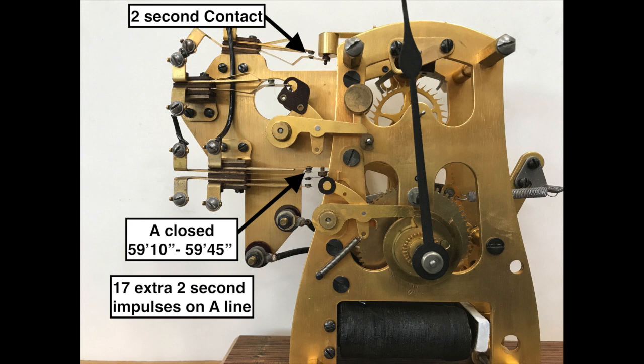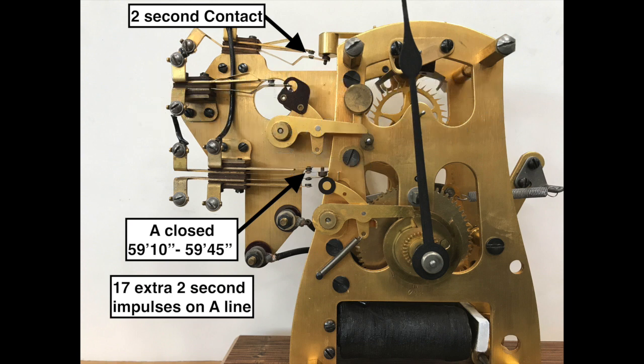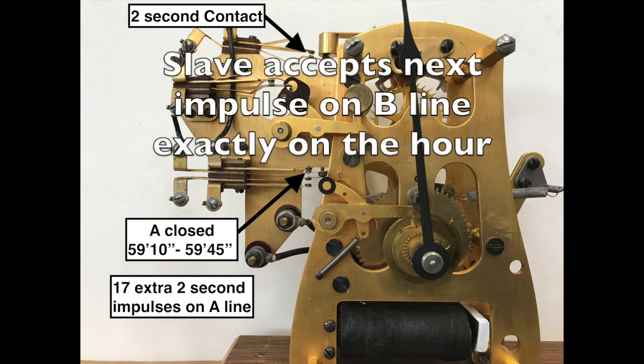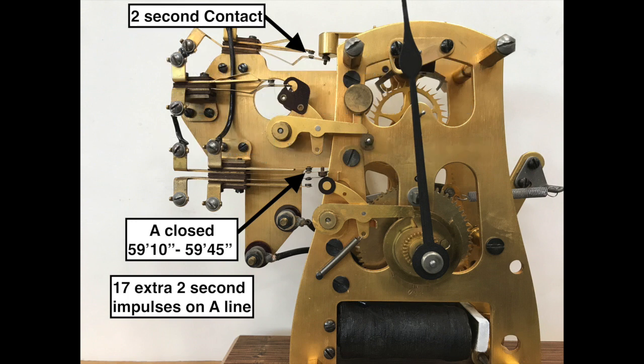At the slave's 59th minute, the AB switch changes the contact from A to B so any additional A line 2 second impulses are not accepted. The slave will accept the next impulse from the master on the B line. This will be exactly on the hour and the synchronization is now complete.